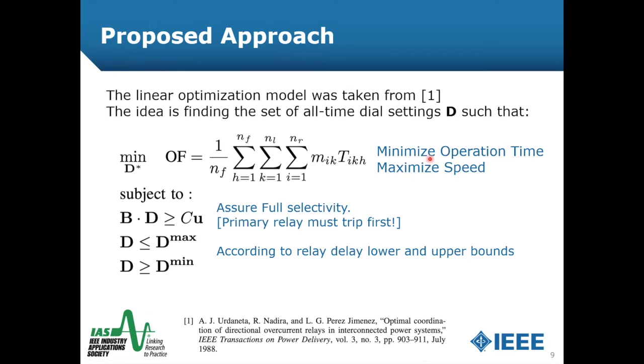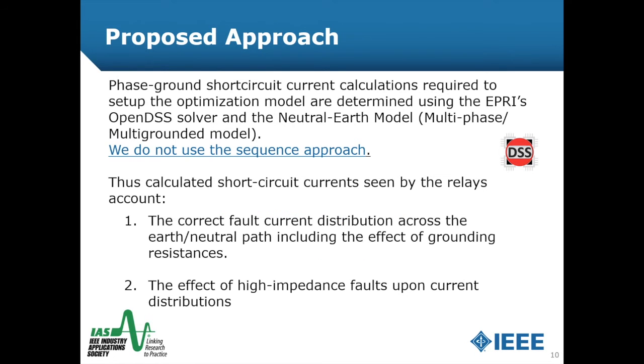Minimizing this objective function will maximize speed, and this will be subjected to the selectivity criteria and the reliability bounds defined by lower and upper limits. In our study, we used the OpenDSS solver and the Neutral Earth model to achieve two main contributions: including the effect of grounding resistance in the earth or neutral path, and assessing the effect of high-impedance faults on the current distribution in the optimization solution.